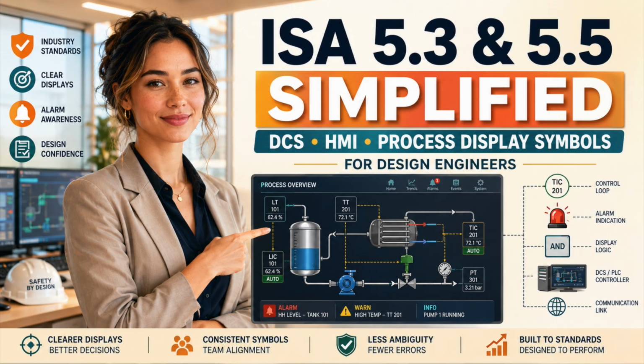That is why color must be treated as a controlled coding tool rather than decoration. When everything is colorful, nothing has priority. If running equipment, process lines, controller modes, navigation buttons, and decorative backgrounds all use intense colors, the display has no visual capacity left when a real abnormal condition appears.